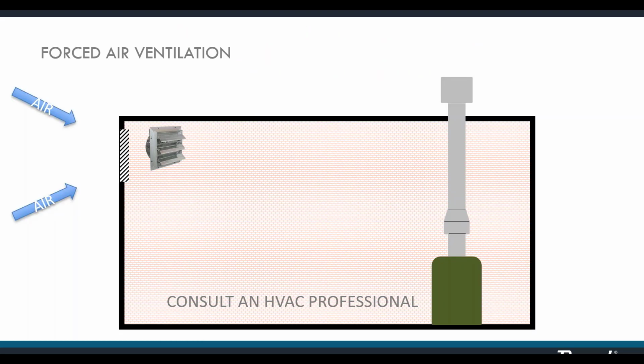If you're installing a heater in a room with a fan that pulls air into the room, that's called forced air ventilation. Generally, you would need an HVAC technician to determine if the fan pulls in enough air to accommodate the gas burning appliances in the room. If you are tuning in today from Texas, the ASME models in Texas have to be low NOx. All right, so you may come across this sort of thing. They require not just any old HVAC guy. You would need a ventilation specialist for that. All right, and they would have to sign off on the room.